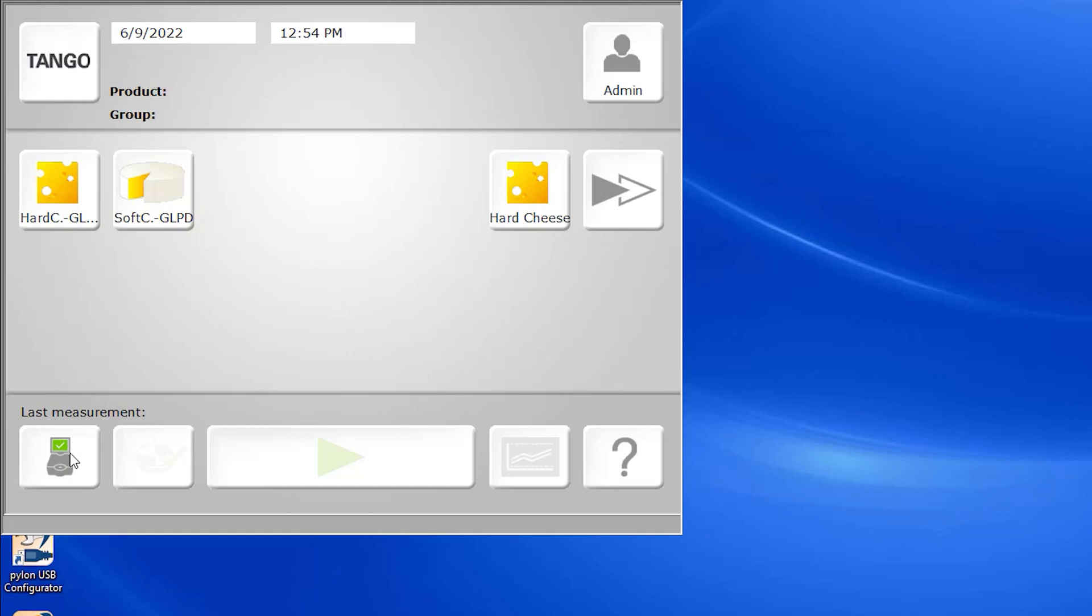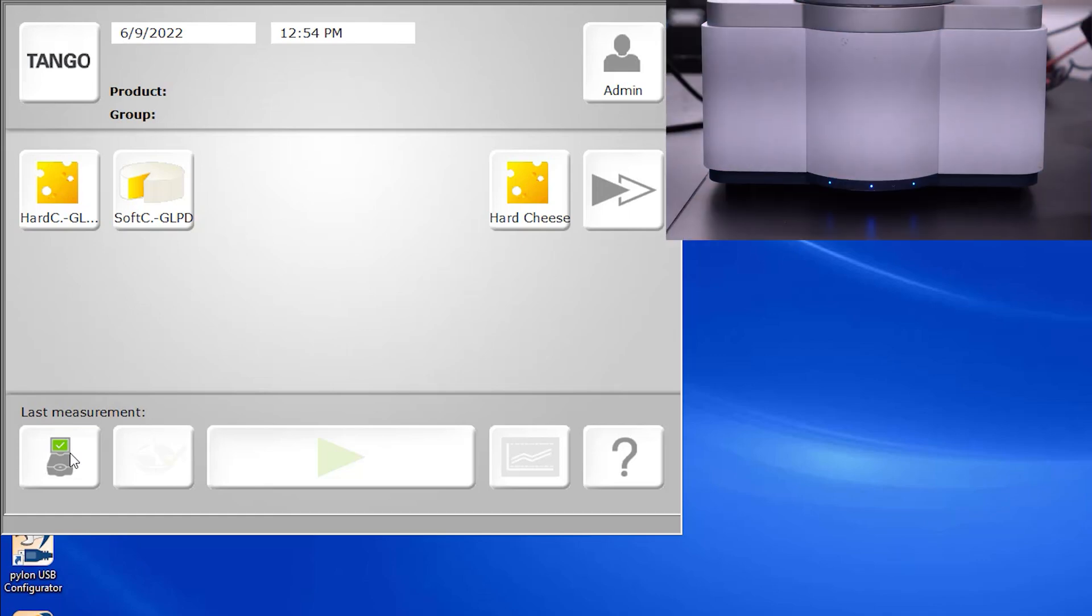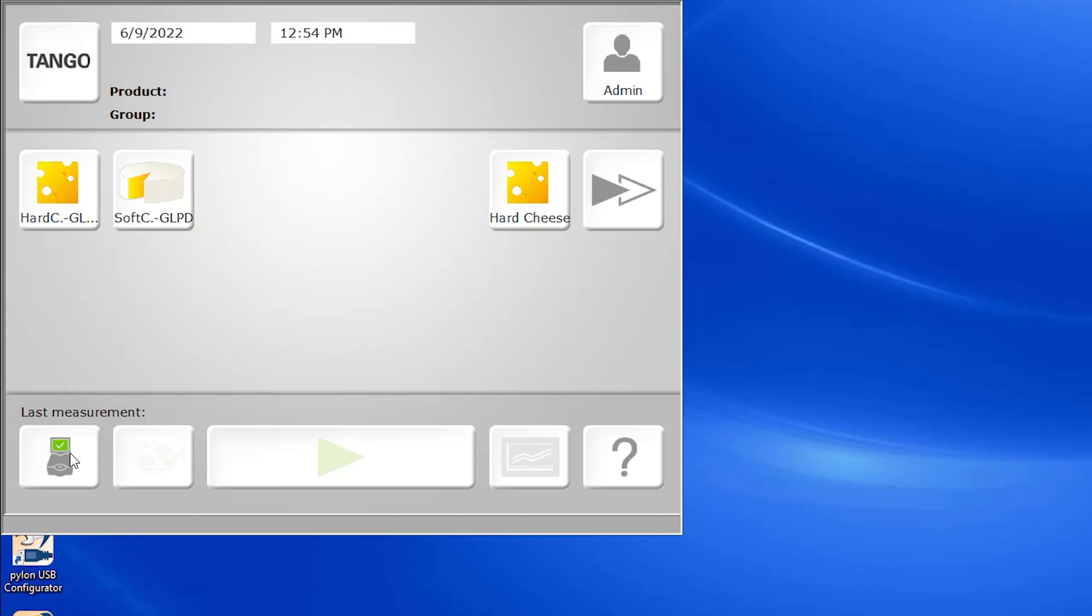When the icon is green, it's indicating that the status of the spectrometer is okay and it's ready for measurement. Similar to the LED lights on the front of the instrument, a yellow colored screen on this icon indicates a warning for either hardware components or it indicates that a diagnostic test needs to be run. While red, however, indicates an error, which signifies that sample measurement will not be possible.